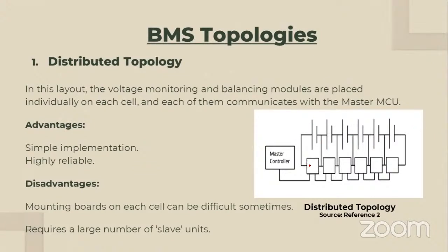Each cell or module will have a slave controller, and all these slave controllers are connected in a cascaded fashion, controlled by one master controller. The communication from the master controller goes to the first one, the first has to communicate to the second controller, the second to the third, and so on. Because of this particular connection method, we will not have any redundancy.